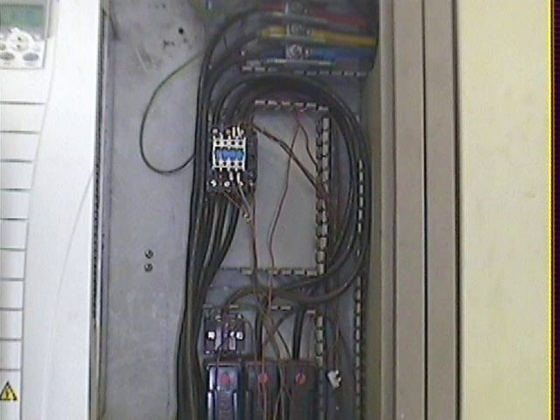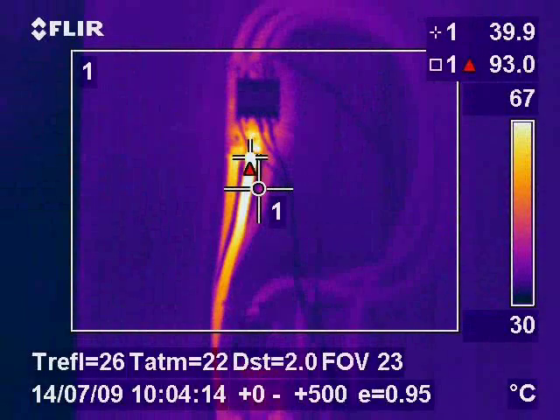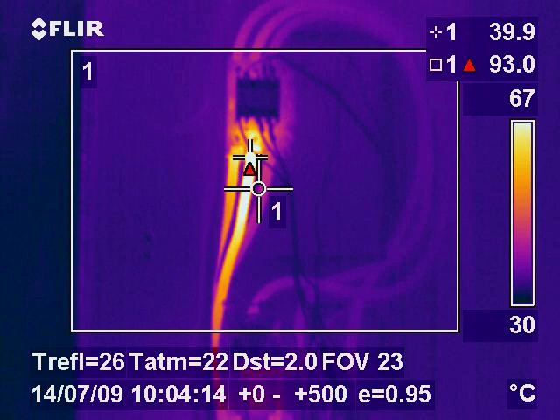In this image we can see a line contactor to the top of the image. This was feeding a VSD. There were no visible faults on the contactor, but in the thermal image we can see a 93 degrees centigrade hot spot caused by a loose connection.